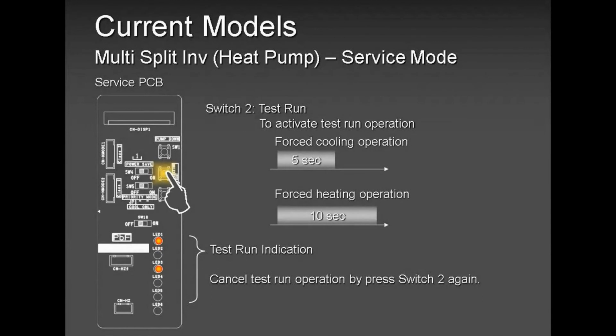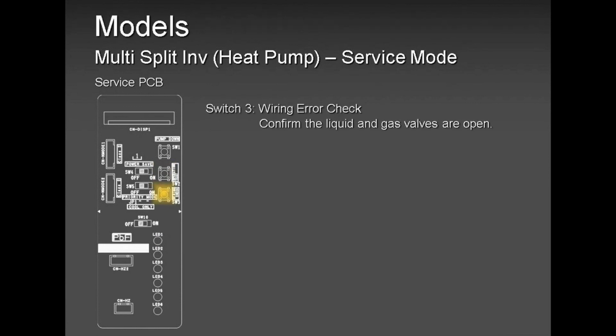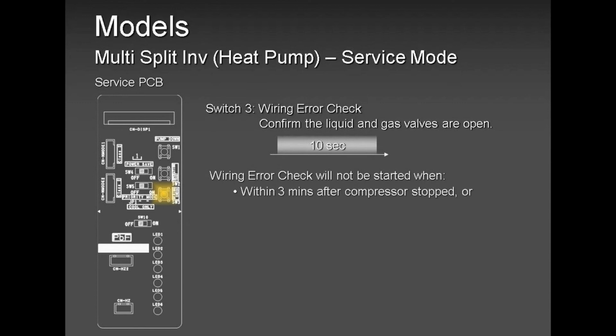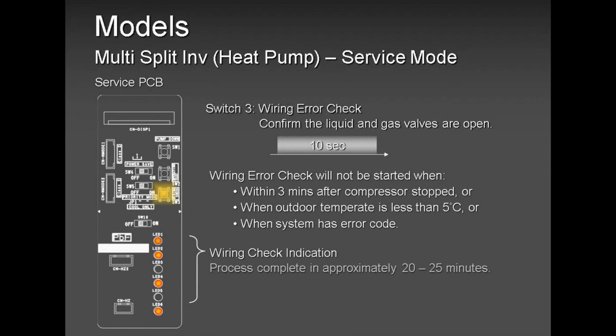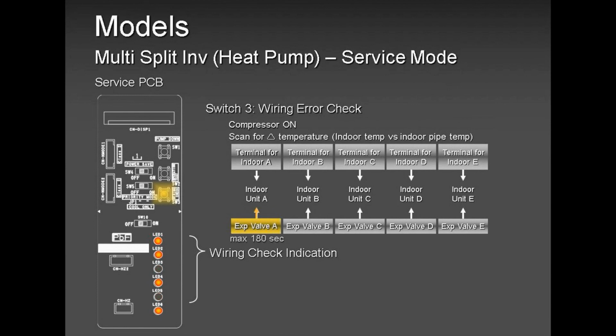Test run. I'm not a big fan of test run unless I have a problem. I always tell my guys, do not perform a test run after you finish installation, because in test run, if you cross the wires, it will not detect that problem. So I always tell my guys, when you're finished with your multi-zone, go inside and turn on one unit at a time to make sure the unit you turn on is giving you good airflow, and if it's in cooling, good cooling, and if it's in heating, a good amount of heat. Because if you cross your wires, that indoor unit will just blow room air, but the coil in another room will be getting hot or cold.